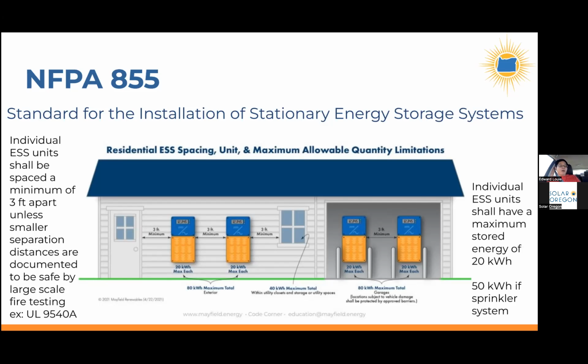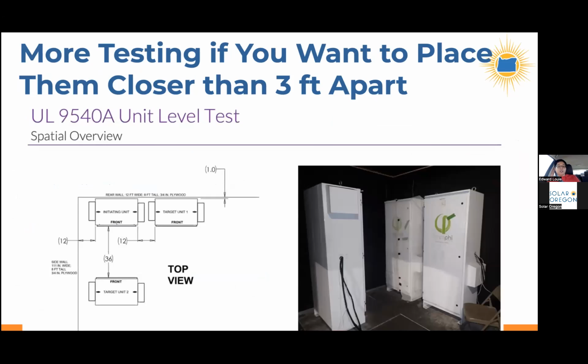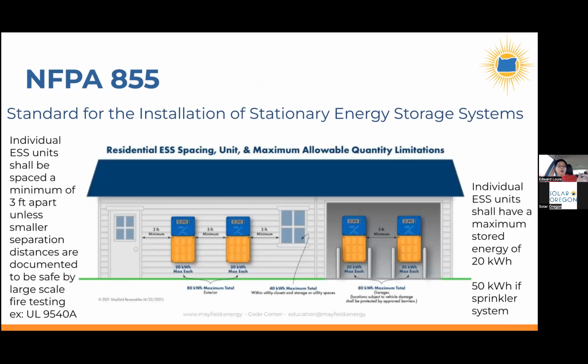And this NFPA 855 standard, they cite the UL 9540A test requirements, and they say you need to put them 3 feet apart unless some battery manufacturer did a UL 9540A test saying that if you put them closer together, it's still safe and the fire doesn't grow to a tremendous size. And so once again, that'll be a test like this, where you have two 20 kilowatt hour racks of batteries placed 12 inches from each other. So with a test like that, you would need to have a test report in order to get away from the 3 feet minimum.